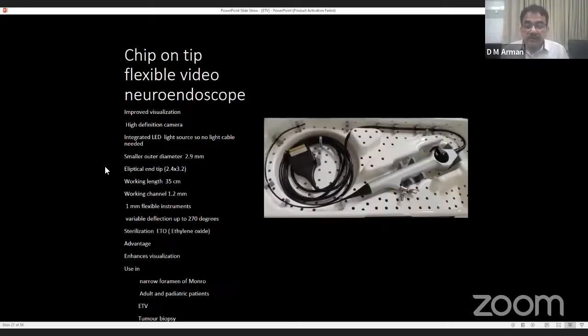We have got recently the latest chip-on-tip flexible video neuroendoscope. The earlier version of the flexible endoscope has limitations. It has poor image quality. This chip-on-tip flexible video neuroendoscope has overcome it. It has improved visualization, a high definition camera, and an integrated LED light source, so no light cable is needed. Its outer diameter is only 2.9 millimeter, with an elliptical end tip, working length 35 centimeter, working channel 1.2 millimeter. 1 millimeter flexible instruments are used in this neuroendoscope.